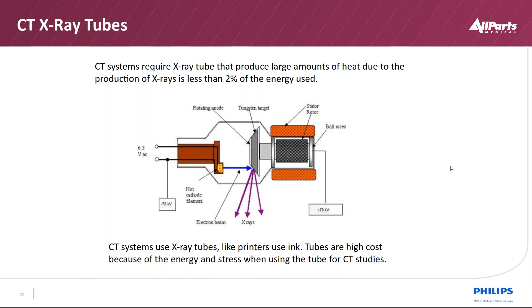that we would have to do depending on what we're doing to troubleshoot. X-ray tubes, like we said, are only 2% efficient. So X-ray tubes become printer cartridges with regards to CT. Average lifespan is anywhere from 22 months to 26 months, obviously about 2 years. That's on an average used machine. Some systems we use more tubes per year. Others, it might be a little bit spread out based on lower usage. But we're dealing with 140,000 volts in the example here. And with only 2% efficiency, we have to make sure everything's clean. All the fans are blowing, oil unit with regards to flow, and then all the filters would be cleaned during PMs as well.